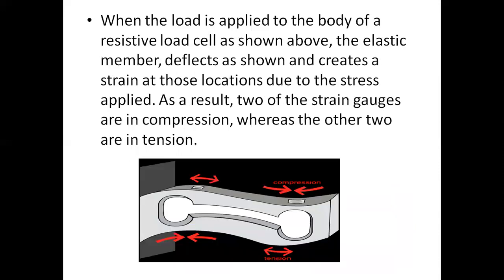During this measurement, the weight will act on the load cell's metal spring element, which causes elastic deformation. This strain will be converted into an electrical signal by a strain gauge installed on the spring element, the simplest type of load cell being a bending beam with a strain gauge. We use a Wheatstone bridge circuit to convert these changes in strain, or resistance, into a voltage which is proportional to the load.